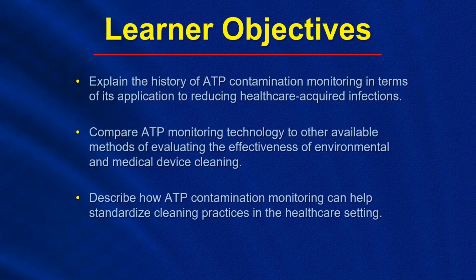Perfect. And another question here is, what is a baseline RLU number as a good surface test? And what is an acceptable number? I know that we were using the Ruhof product, and I believe that they have their second or third generation device out now, and I think that based on the independent research, the acceptable number is 100. Anything below 100, and you can confirm that by going to the Ruhof site. I don't use them personally, but I believe 100 is the number, and we can confirm that if that person wants to reach out to Ruhof or send a note. I'm pretty sure the number is 100 or less.